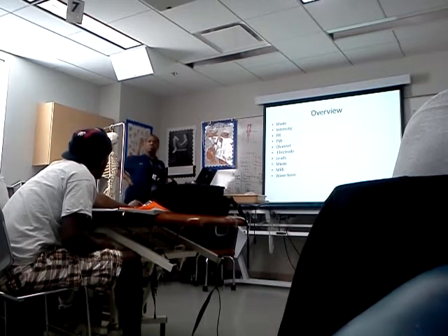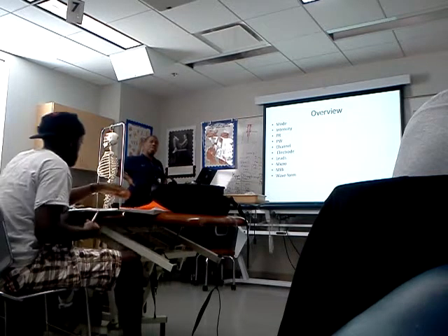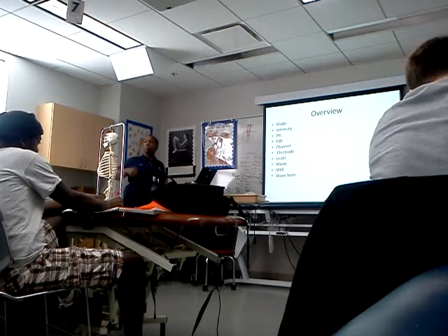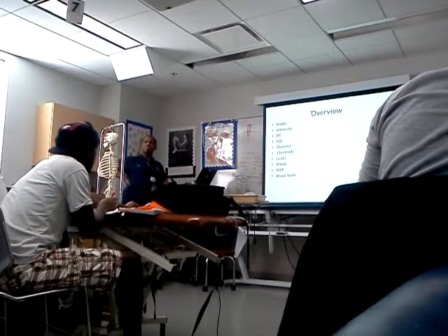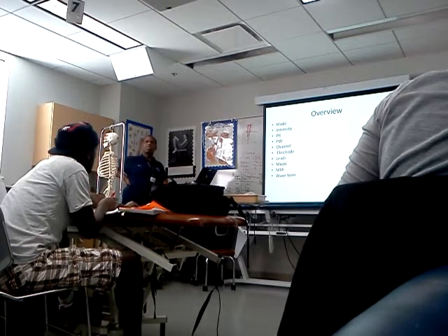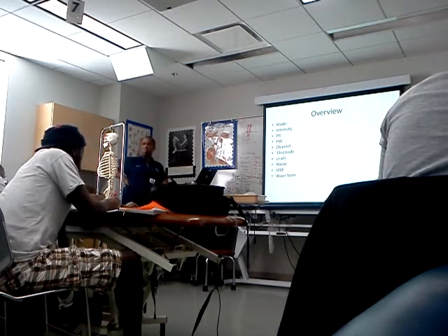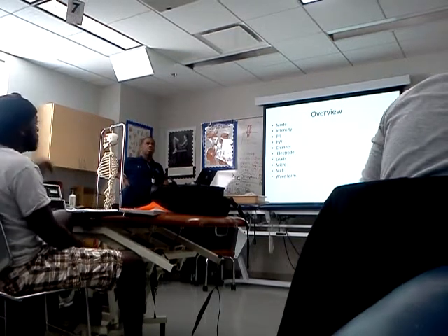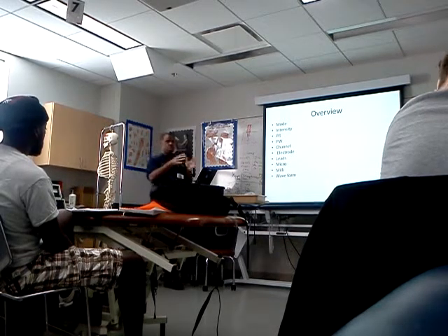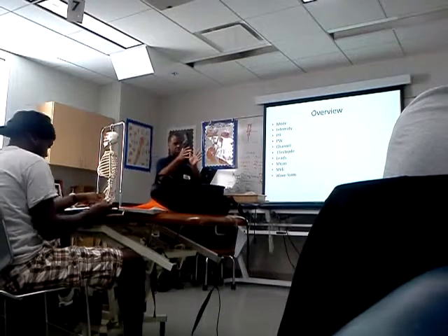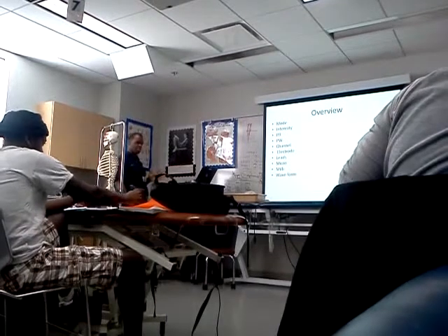What is meant by electrode? Those are the pads. Good. All right. What is meant by leads? The wires that go into the electrode. Good. All right. Micro is referring to what? Seconds for which parameter? Pulse width. All right. And then milli also, milliseconds too. Which one is wider? Milli is wider. All right. So if you go back to the duration curve, you have microseconds, and then it extends into milliseconds.